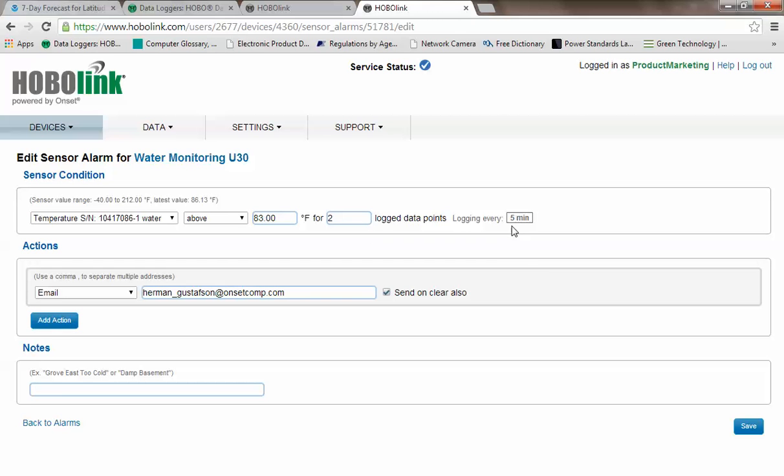It's important to understand that alarm notification is based on logging interval, not on connection interval. What this means is if you're logging every five minutes, but scheduled to only connect to HoboLink once an hour, if you go into alarm condition, you will be notified at the next logging interval, or in five minutes.